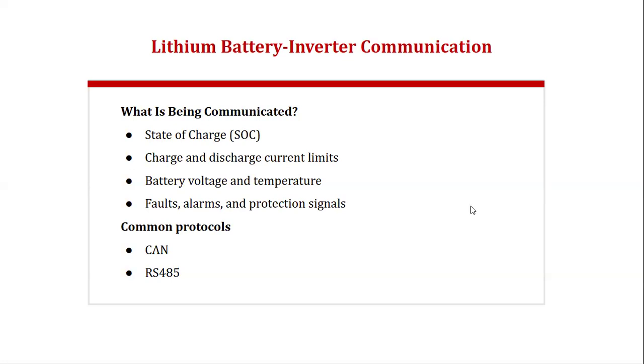The battery voltage and temperature, yeah. When it's rising in temperature, maybe the environment is a little bit hot. Of course, we are not supposed to put your battery in a place where it's going to be hot. But for instance, maybe the battery has been in operation and it senses a rise in temperature. The BMS will control many parts of the system. Oh, temperature is rising. Okay, charging, reduce, until the temperature is reduced so that I can fire on with the batteries.